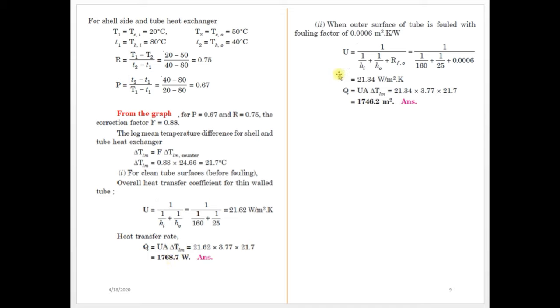Now we will consider with the fouling factor. The fouling factor RF value is given — consider that 0.0006. Find U = 21.34 W/m²K, then find Q value by substitution. The result is Q = 1746.2 W.